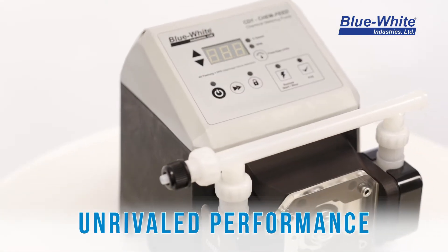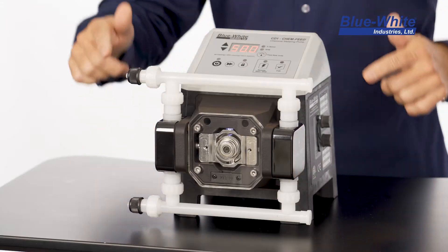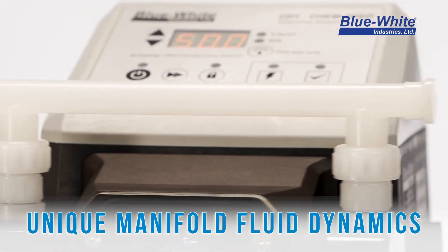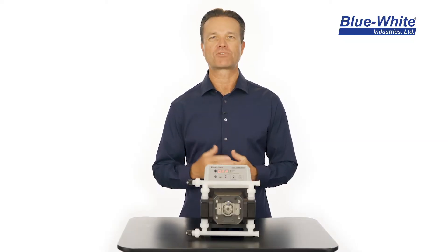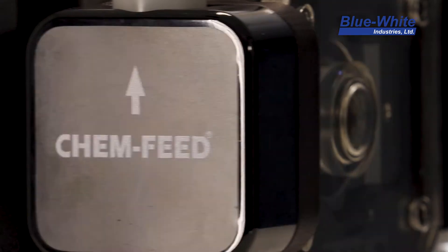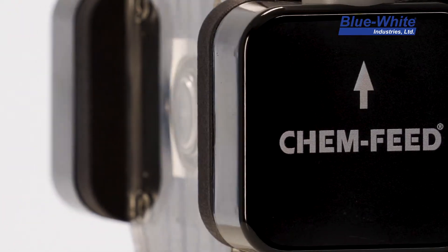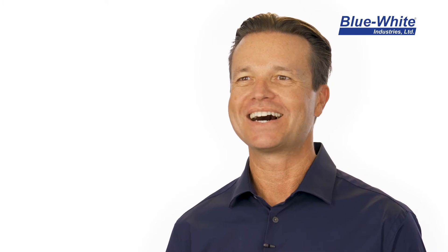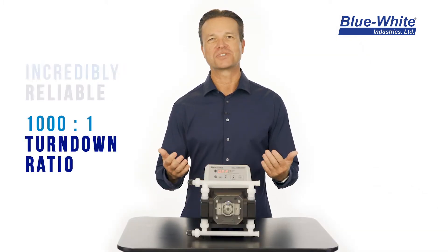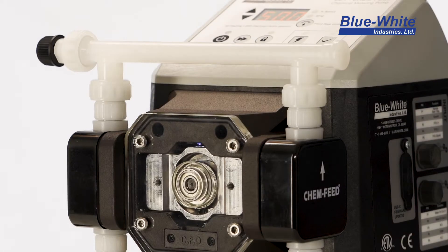Our metering pump technology will pump chemicals continuously, similar to a peristaltic pump, without ever replacing a tube. The CD-1F can outperform many existing technologies in the marketplace today. The increase in performance is due to the manifold's unique fluid dynamics, created from each diaphragm working in a separate phase. When one diaphragm is in the suction phase, the other is in the discharge phase — this repeating cycle allows us to achieve an incredibly reliable pump with flow characteristics that can outperform a peristaltic metering pump.